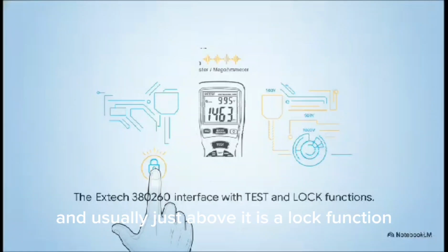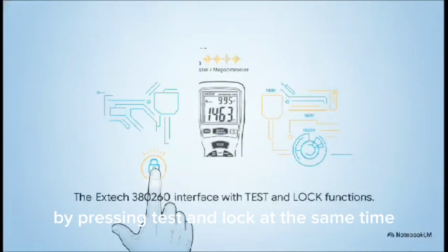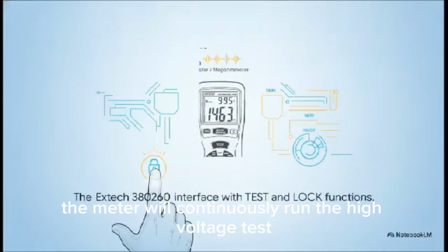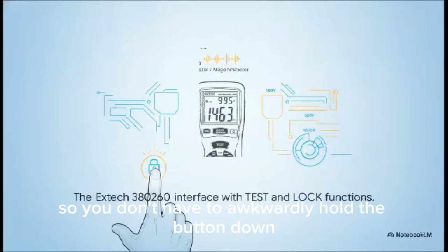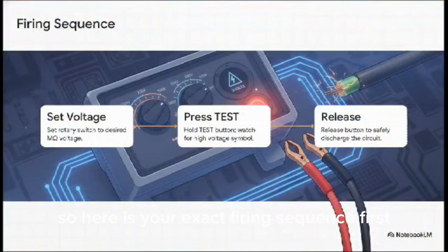And usually, just above it is a lock function. Now that lock is a fantastic little feature for hands-free operation. By pressing test and lock at the same time, the meter will continuously run the high voltage test, just beeping every couple of seconds so you don't have to awkwardly hold the button down yourself. So, here is your exact firing sequence.